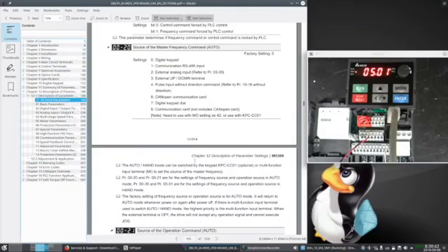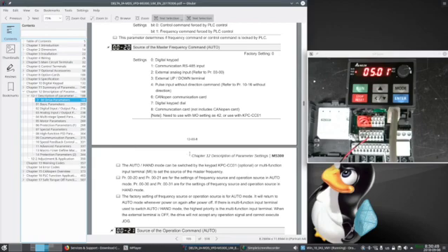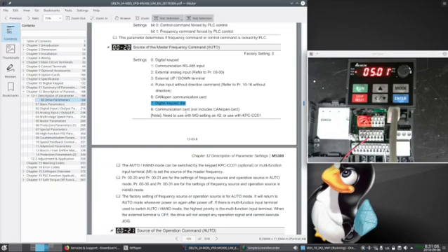Two very important parameters are where does the drive get its speed reference from, and its commands from. Those are parameters 20 and 21. So to run from the dial, I must set 20 to a 7.